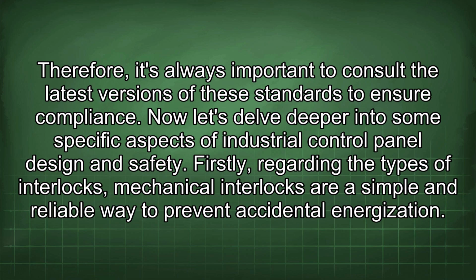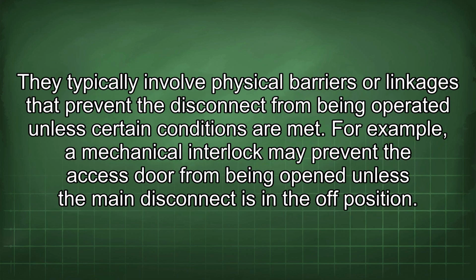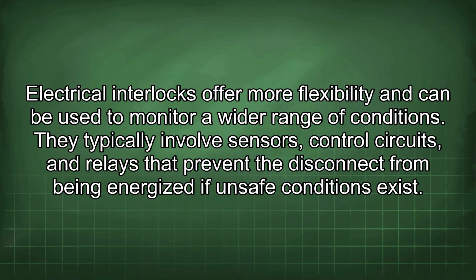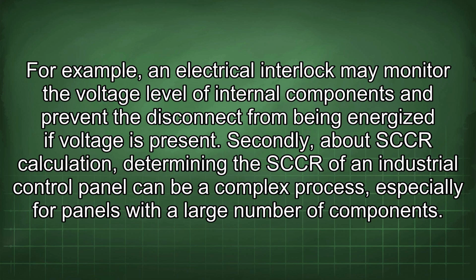Firstly, regarding the types of interlocks, mechanical interlocks are a simple and reliable way to prevent accidental energization. They typically involve physical barriers or linkages that prevent the disconnect from being operated unless certain conditions are met. For example, a mechanical interlock may prevent the access door from being opened unless the main disconnect is in the off position. Electrical interlocks offer more flexibility and can be used to monitor a wider range of conditions. They typically involve sensors, control circuits, and relays that prevent the disconnect from being energized if unsafe conditions exist.